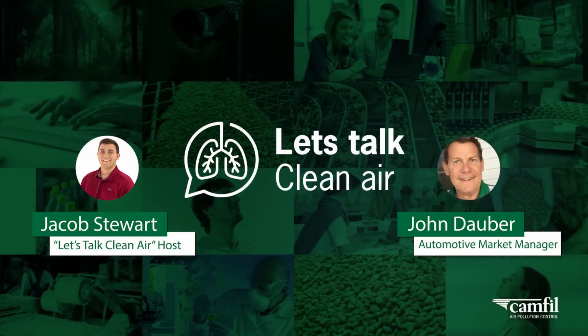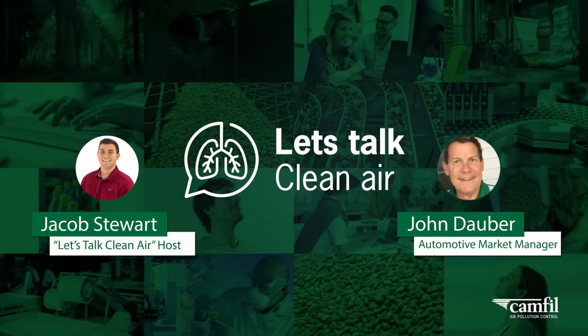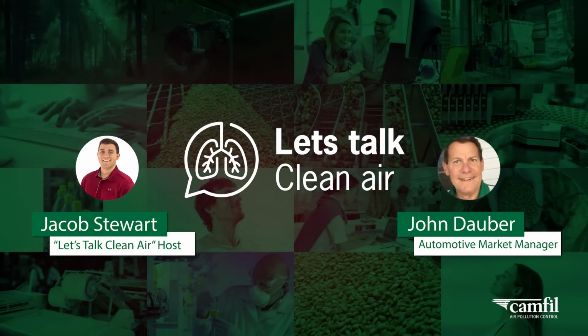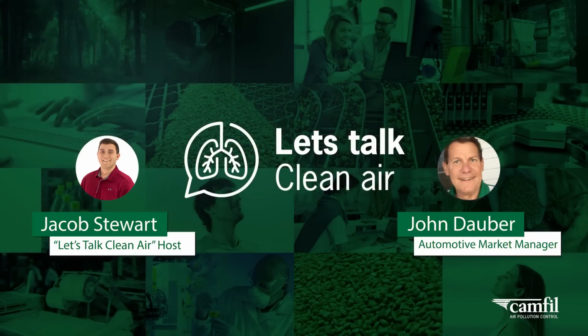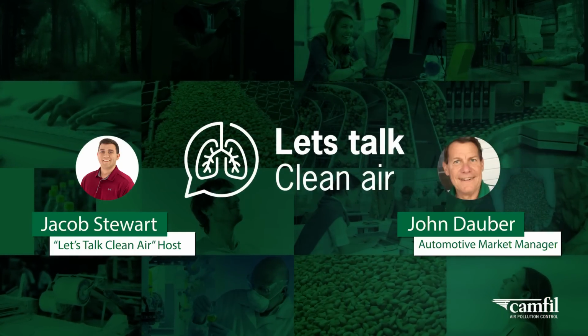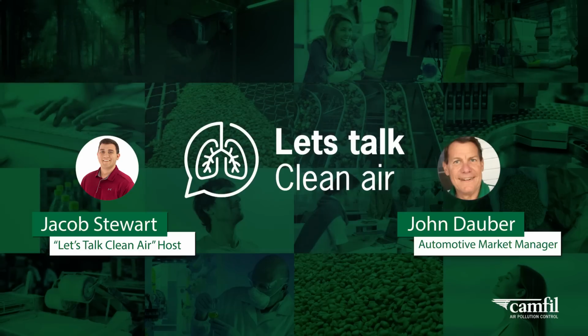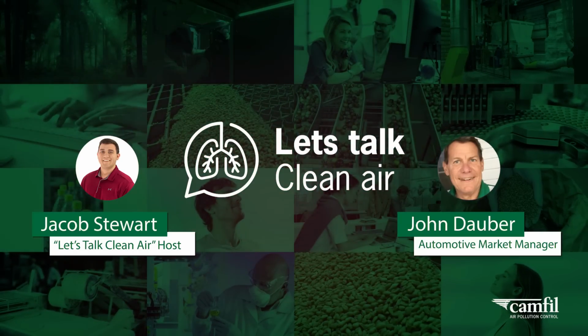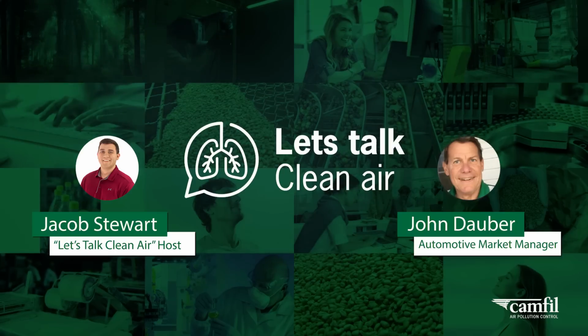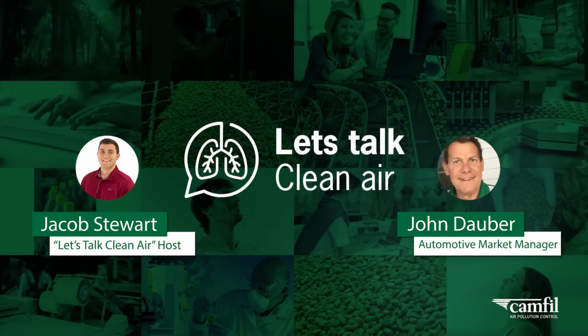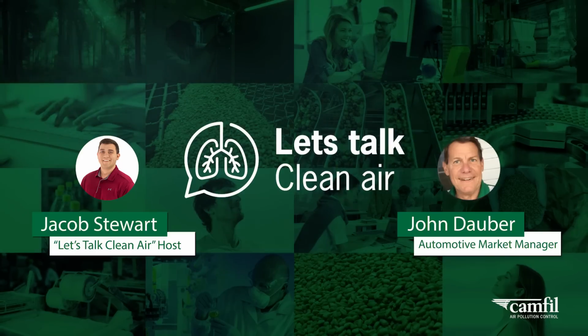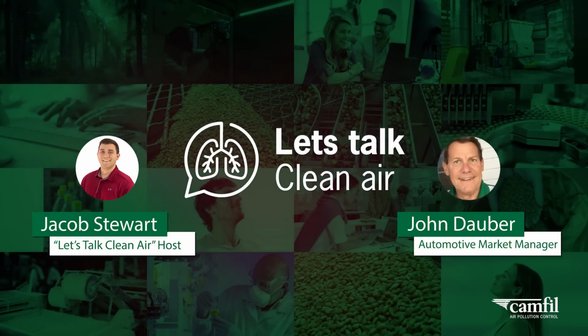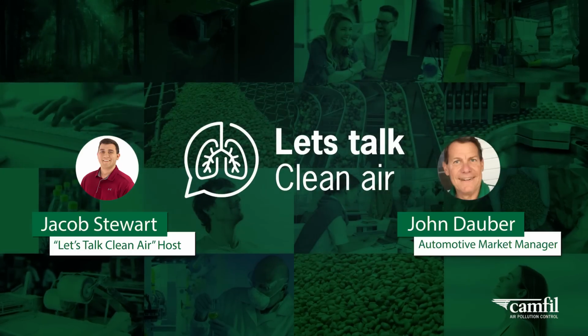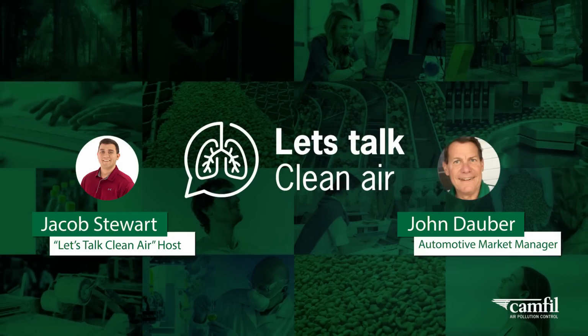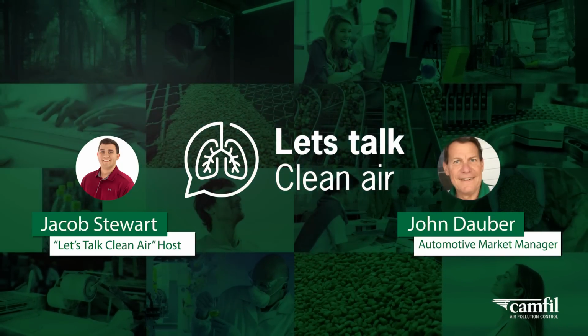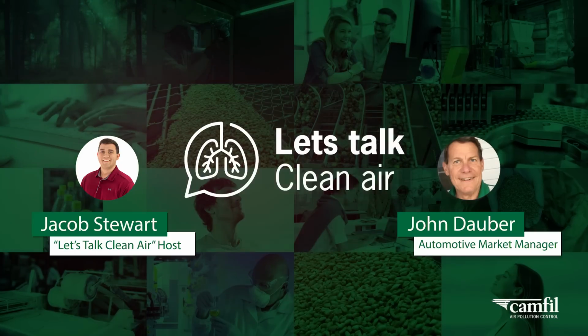But then when we go to fire suppression, which in some cases when the KST value is really high, or you can't put explosion venting on it either because of the location of the collector or the type of dust we're dealing with. And it's basically it senses that an event is starting to happen and it floods the vessel and the ductwork with sodium bicarbonate. And it basically takes out the oxygen in the air, and that takes out one part of that dust explosion pentagon that we talked about earlier. So it stops the explosion before it happens.